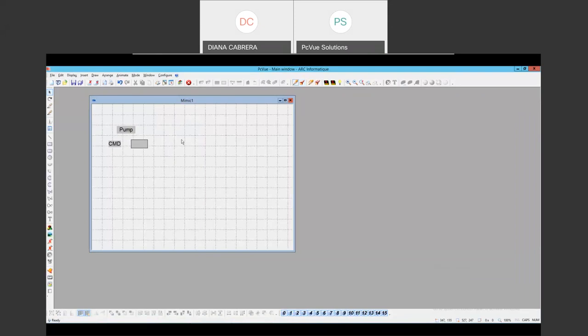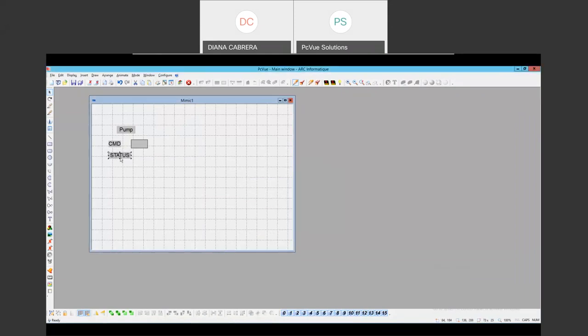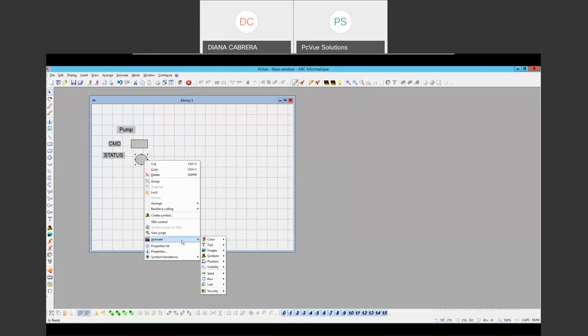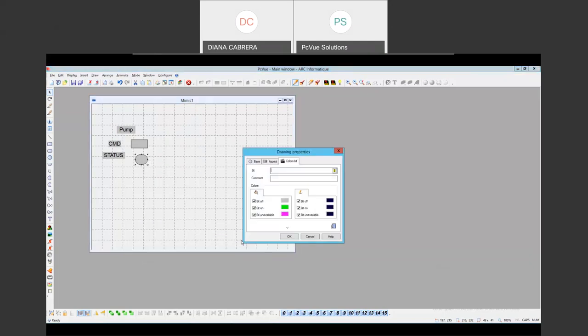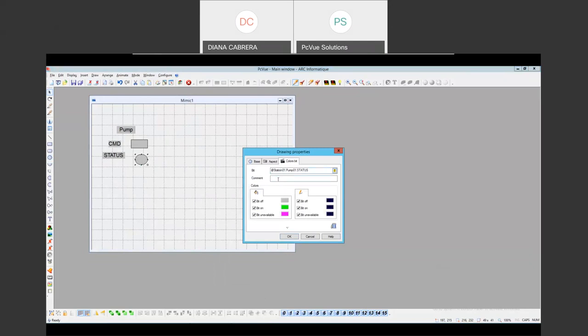I'm going to continue adding some objects to my mimic — for instance the status variable. I'm going to use another object and a new animation: color bit. I'm going to look for my status variable. Here we can add a comment, and we can see that if the bit is off the color will be gray, if the bit is on it will be green, and if the bit is unavailable it will be pink. We can also change the contour.